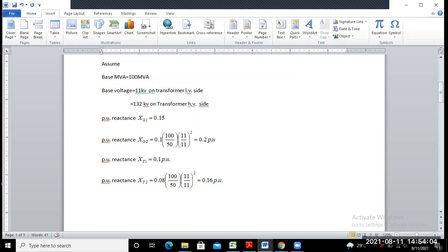Generator 1, generator 2, transformer 1, transformer 2, reactance values are provided to you in per unit. But the transmission line reactance value is not given in per unit. Its value is given in actual unit, ohm. So how can we convert that reactance value into per unit? Just tell me. First of all, find out the total reactance of the transmission line per phase.